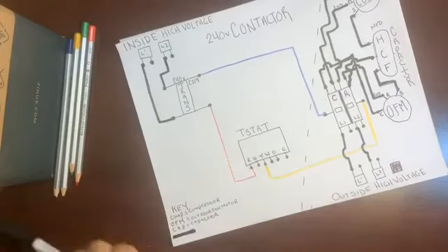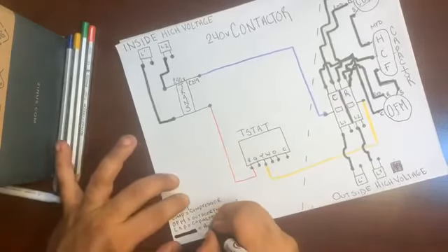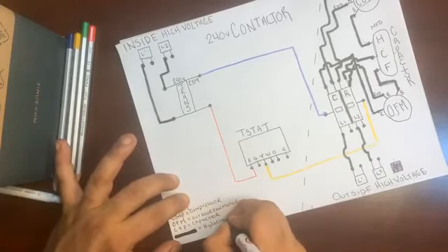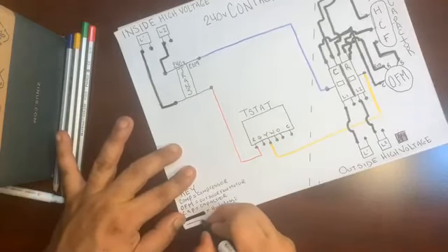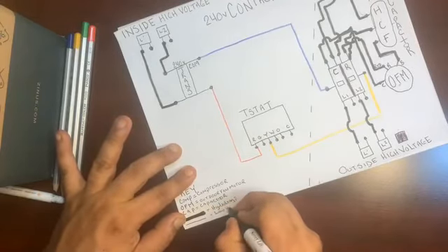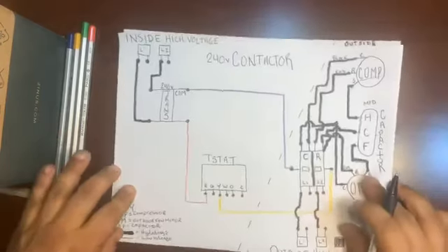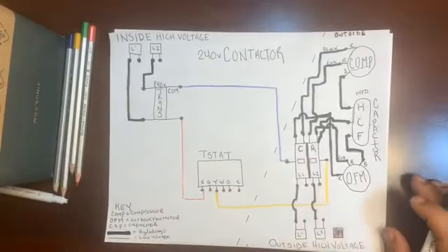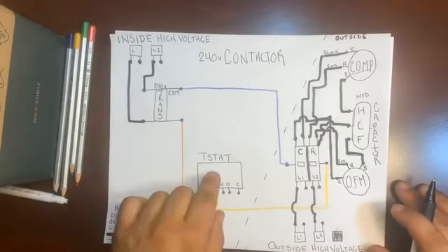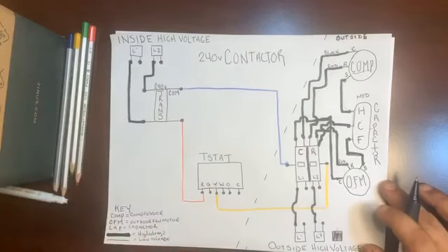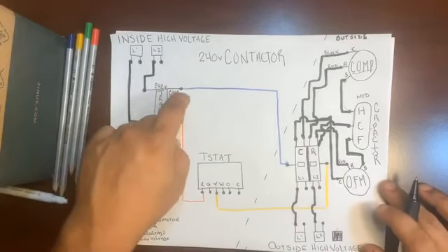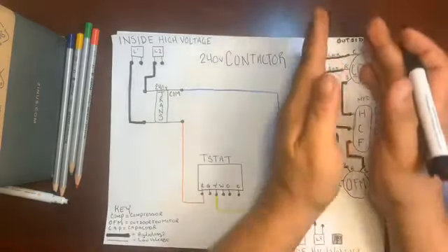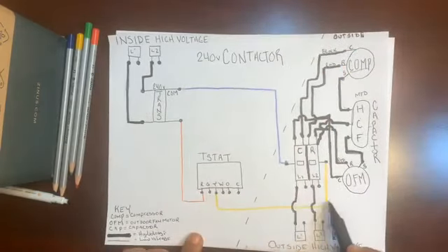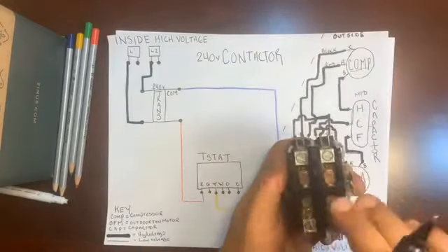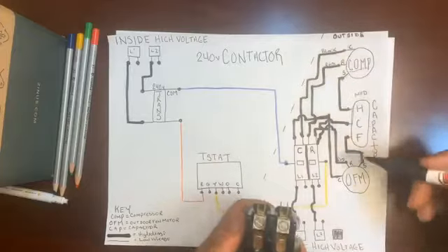Thick line equals high voltage, and of course our thin line is going to equal low voltage. We're slowly putting it together, but just realize again, the very grasp of all of this is low voltage and relays are made possible by the transformer. If there was no transformer stepping voltage from 240 down to 24, we wouldn't be able to control all of this high voltage with nothing but one little yellow wire saying engage and control high voltage with low voltage, because that's the relay game.